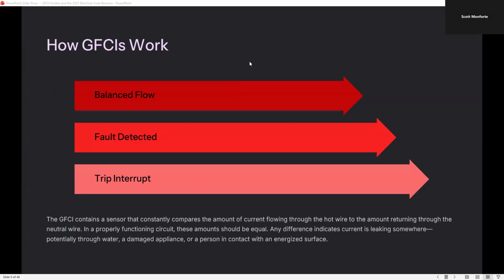So how does it work? We have a balanced flow, a fault is detected, and a trip is initiated. The GFCI contains a sensor that continuously compares the amount of current flowing through the hot wire to the amount returning through the neutral wire. You can think of the neutral wire as a path where the electricity goes. We're not taking all the amperage from it, just a little bit. In a properly functioning circuit, these amounts should be equal. Any difference indicates current is leaking somewhere, potentially through water, a damaged appliance, or a person in contact with an energized surface.